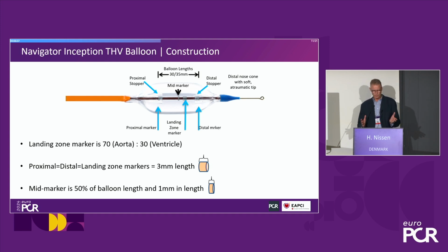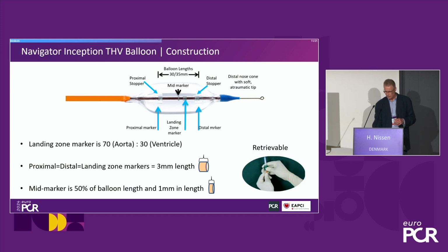Another advantage, or a very important advantage, is that it is retrievable. So occasionally, when you put on balloon expandable valves, even though it's a 14 French system or a 16 French system, you have to take account when the valve comes in, it's quite a bit larger. So you occasionally need to prepare the vessel. And in this case, you don't have to be so forceful when you start preparing the vessel, because you have a bailout, you can take it out and do some more prepping on the vessel, which is a quite nice feature.